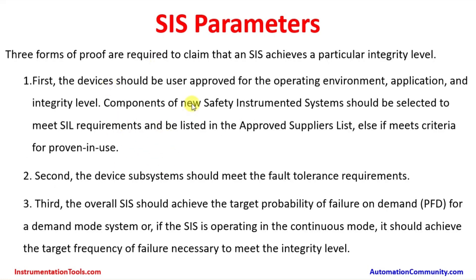The first requirement is that devices should be user-approved for the operating environment, application, and integrity level. Components of a new safety instrumented system should be selected to meet SIL requirements and be listed in the approved suppliers list, or meet the criteria of 'proven in use' — meaning the same type of instrument is used in a different plant with an identical installation in a similar geographical zone where ambient and environmental conditions are typical. Instruments used in Western countries cannot be directly applied in Asian or Asia-Pacific regions due to differing environmental conditions.